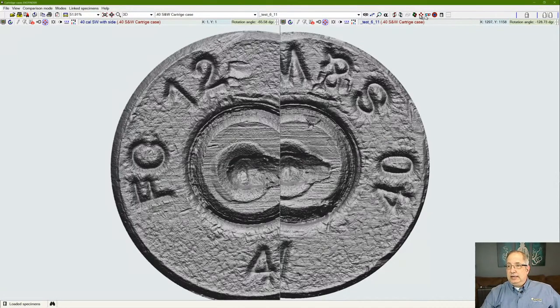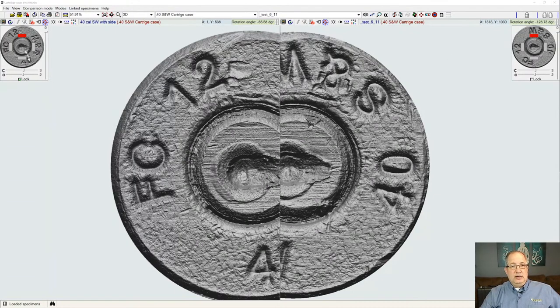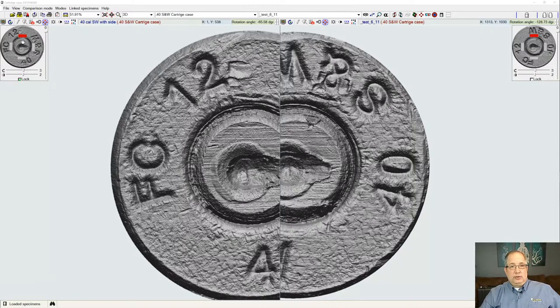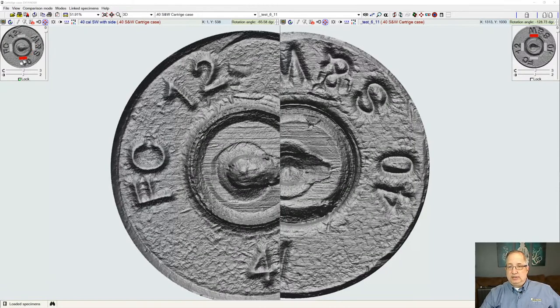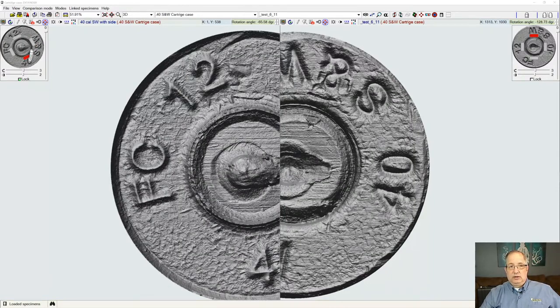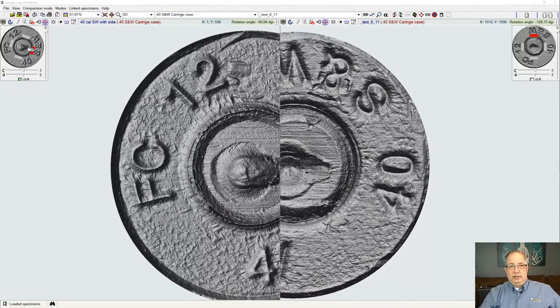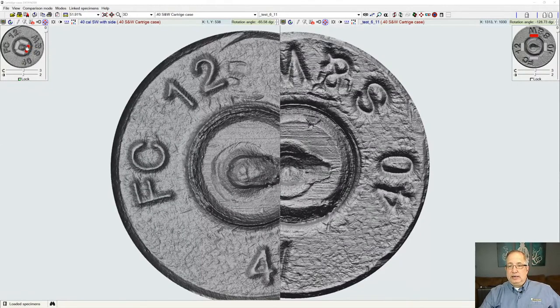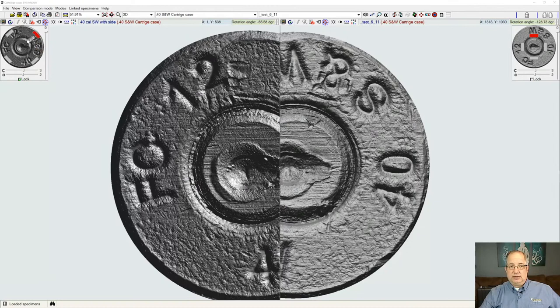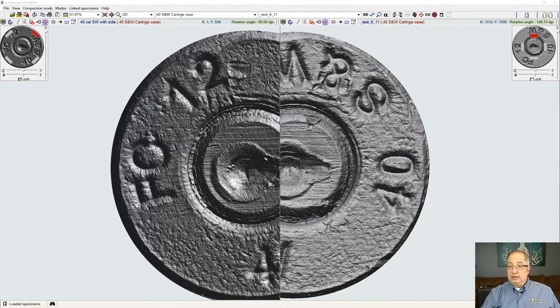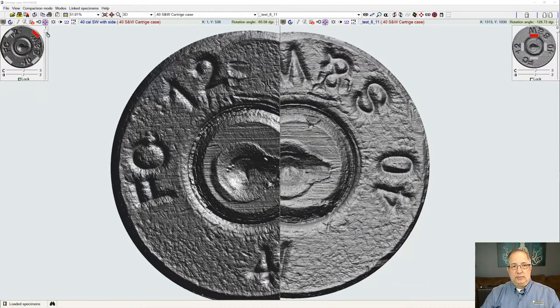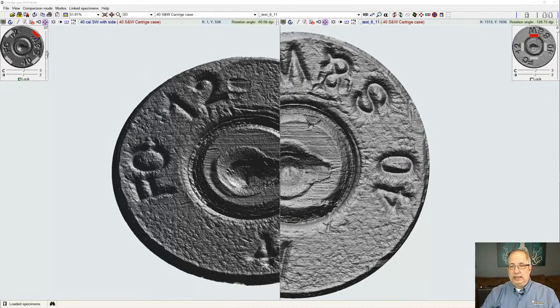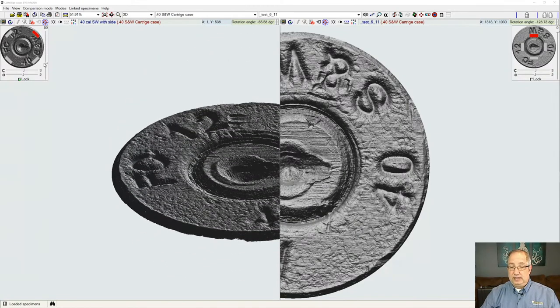We can change the contrast of the sample itself for the examination. The lighting controls allow us full control around the sample where we can lock that as we change rotation, and we can use this to go either rotationally around the optical axis, or we can use it to go on axis or more oblique, again changing the contrast. We can also tip the samples back in the Z axis so we can gain an oblique view of the sample itself.